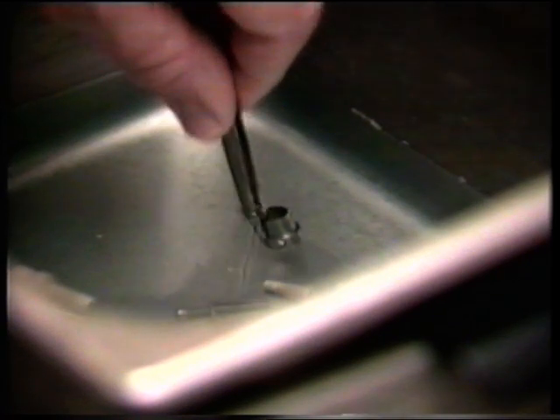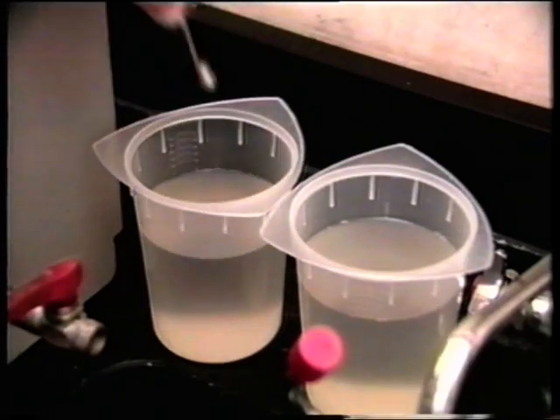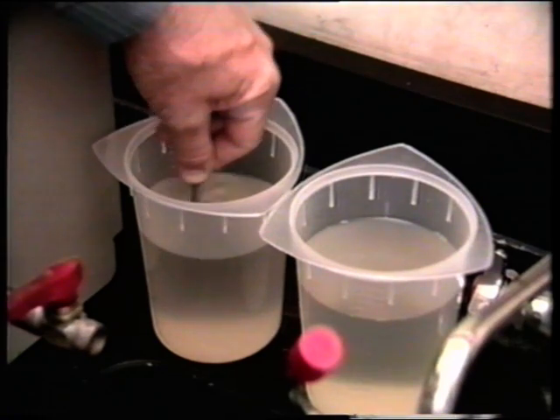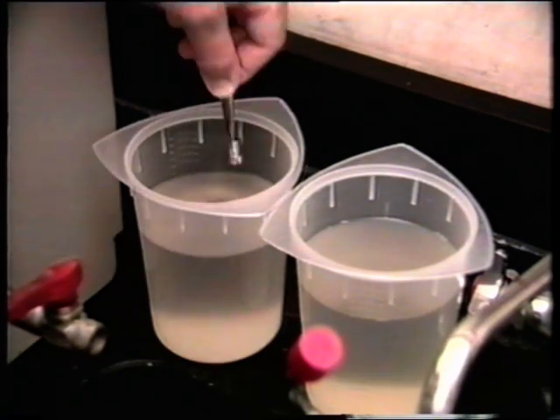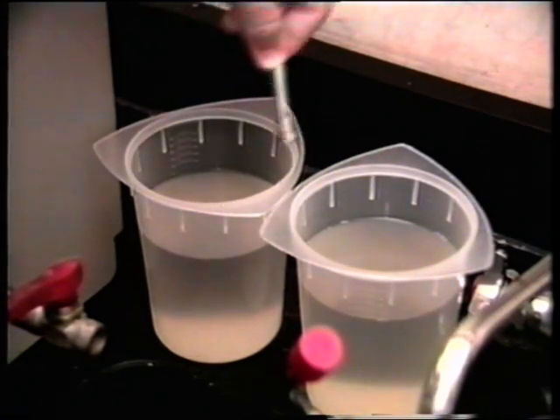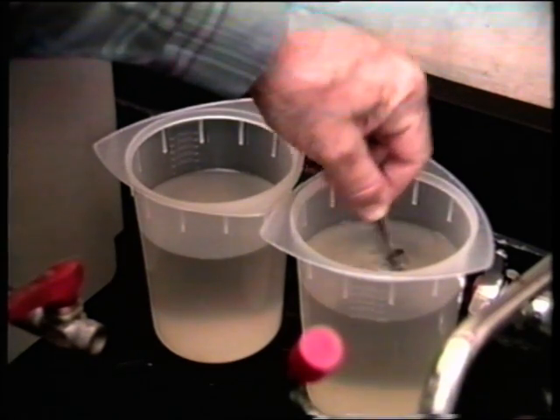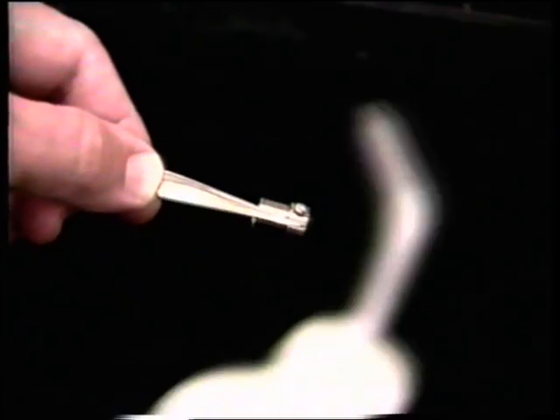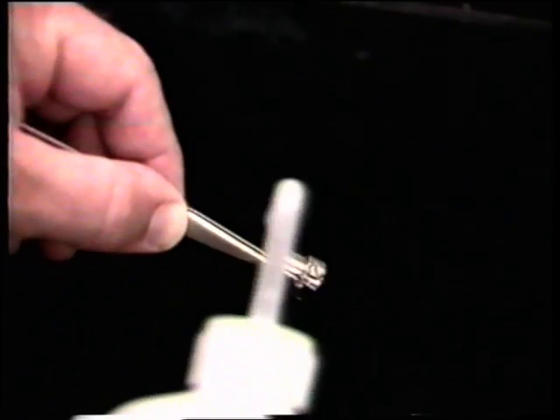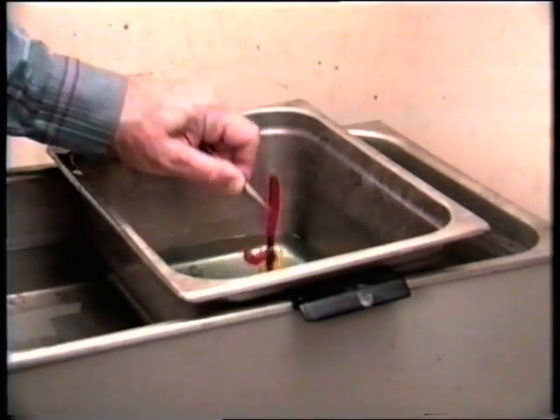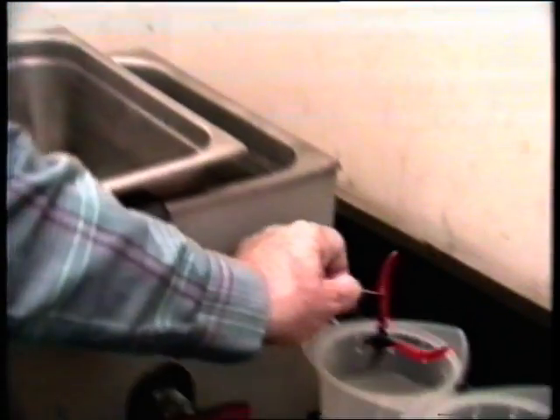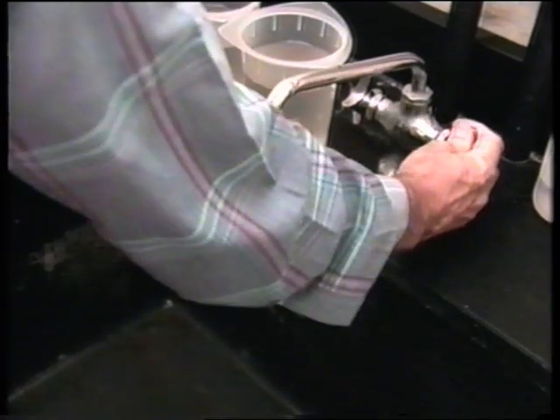All pieces of the detector, except the air filter disc, should be ultrasonically cleaned to remove any contaminants that could give false indications when the detector is restored to operation. Use a degreaser on each piece to remove the ultrasonic cleaning solvent. Clean all parts with warm soapy water to remove the degreaser, and rinse all parts with distilled water to remove any soap film. Clean all hand tools in the same manner, and be sure to wash your hands.